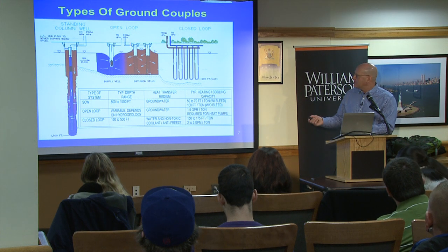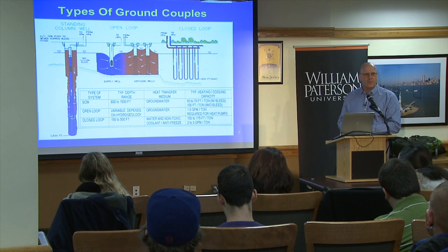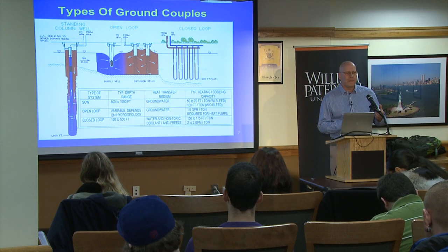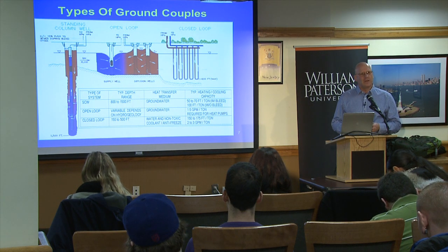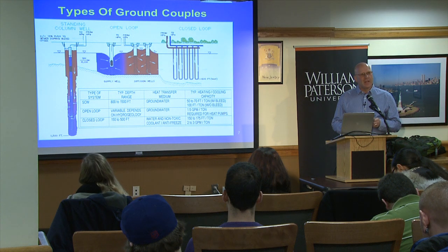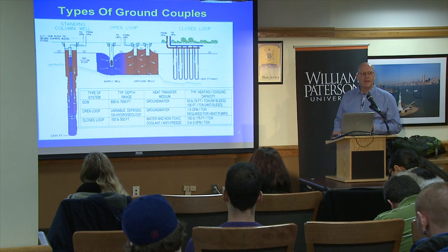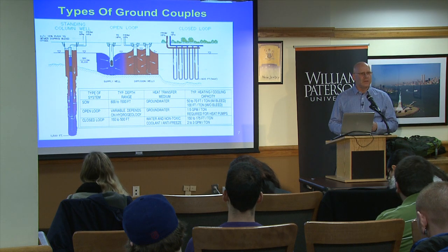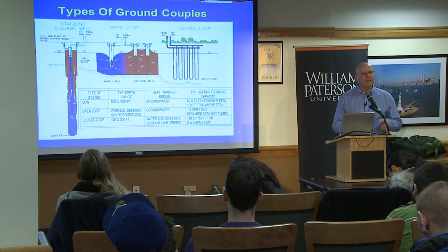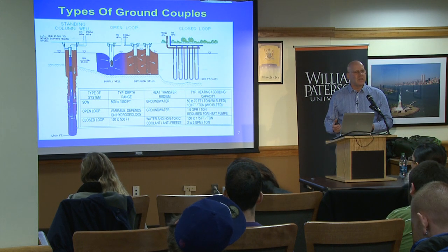But in practice, you need at least 2 for 1, sometimes 3 for 1. So working with water is the best way of exchanging heat with the earth, but it's also a chemical challenge and a mechanical challenge, because you also have a pump that's in the ground. Now you have a component of your heating and cooling system for a building that's not in the building. And conventionally, engineers who design buildings, they don't like that.